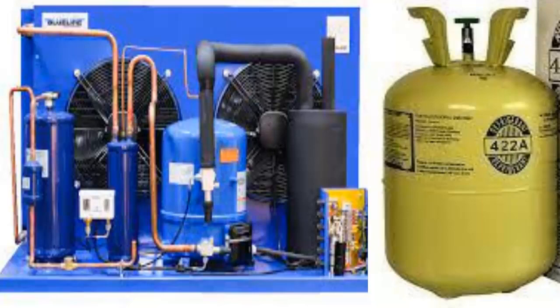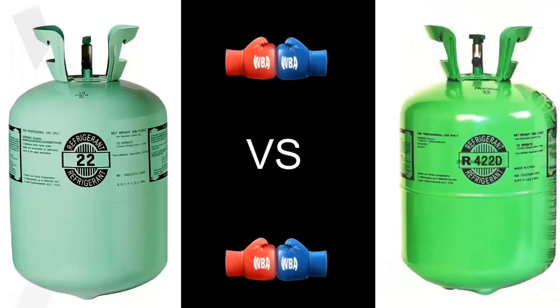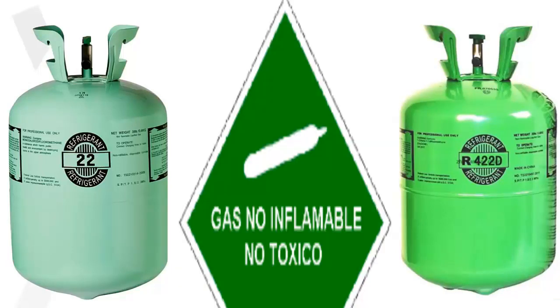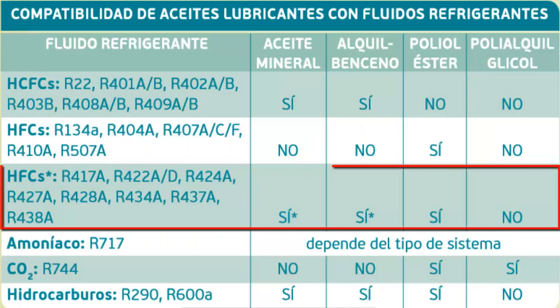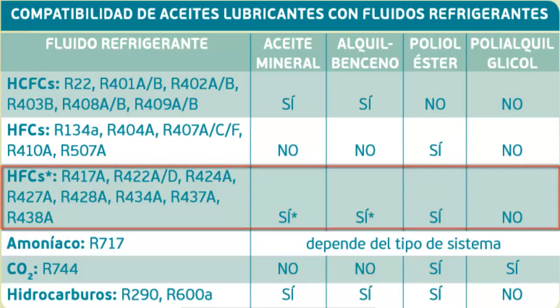Both R22 and gases in the R422 family are non-flammable and non-toxic, classified as A1 in terms of safety, and belong to group L1. These refrigerants are compatible with a variety of lubricants, including mineral oil (MO), alkylbenzene oil (AB), and polyolester oil (POE).